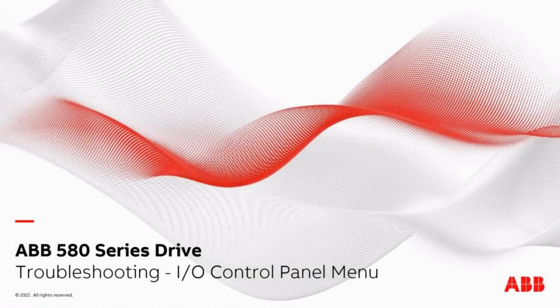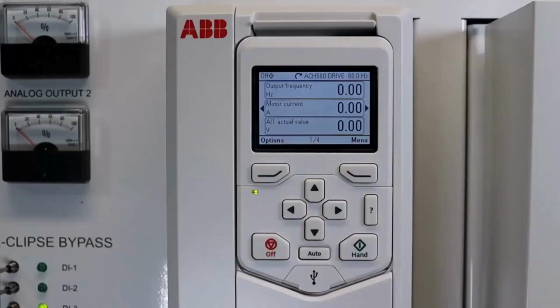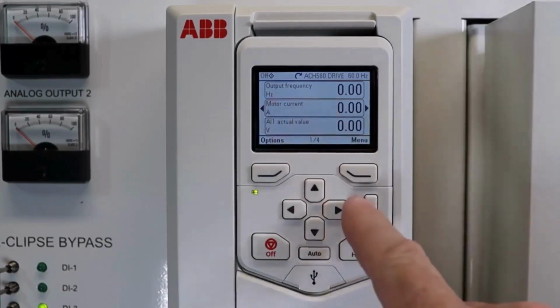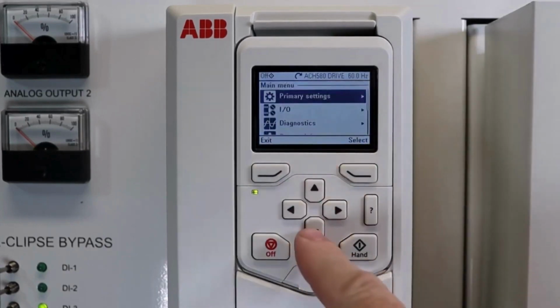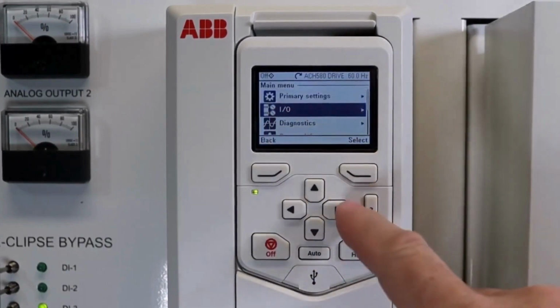In this short video, we're going to look at the ABB 580 series drive, troubleshooting through the I/O control panel menu. We are going to take a look at the ACH580 drive, and we're going to look at I/O monitoring and I/O testing through the keypad using the I/O test area. All we have to do is hit menu. We can go down to I/O, hit select.